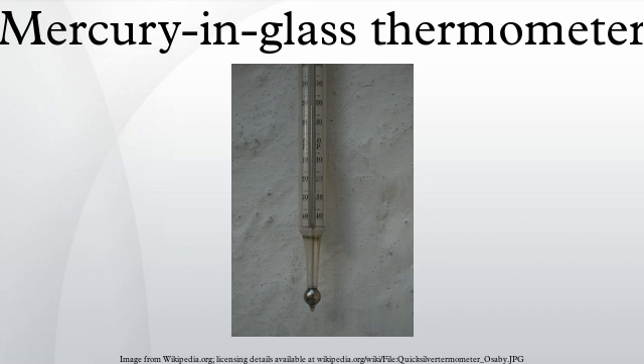Finally, Celsius proposed a method of calibrating a thermometer: place the cylinder of the thermometer in melting ice made of pure water and mark the point where the fluid in the thermometer stabilizes. This point is the freeze-thaw point of water. In the same manner mark the point where the fluid stabilizes when the thermometer is placed in boiling water vapor. Divide the length between the two marks into 100 equal parts. These points are adequate for approximate calibration but both vary with atmospheric pressure. Nowadays, the triple point of water is used instead of the freezing point, 0.01 degrees Celsius.